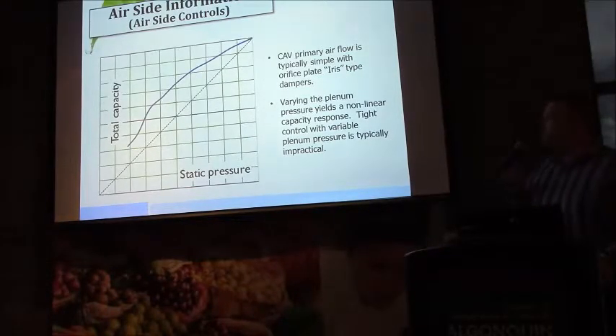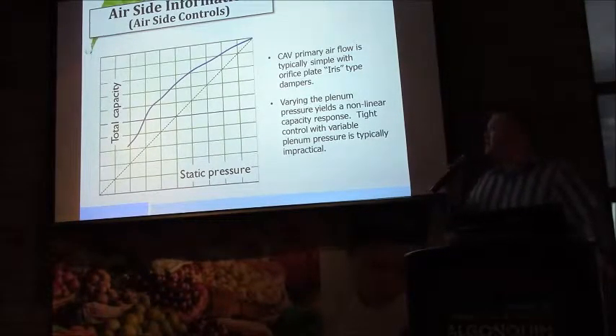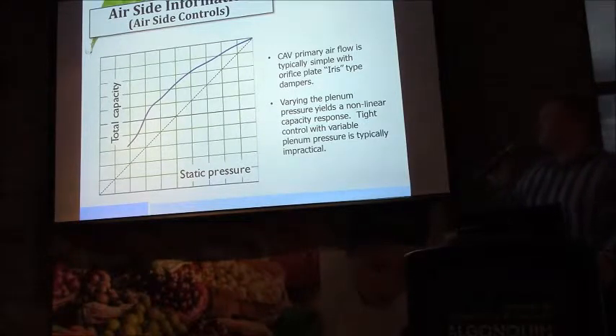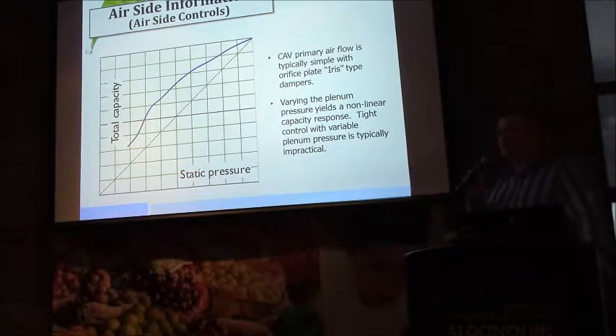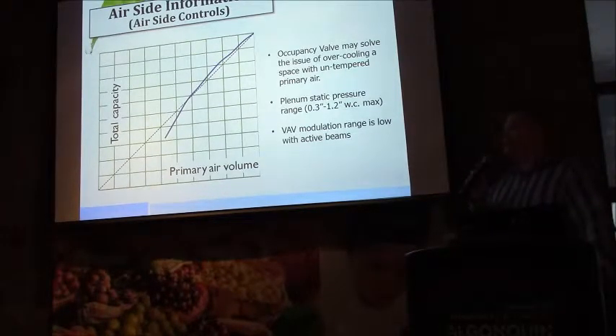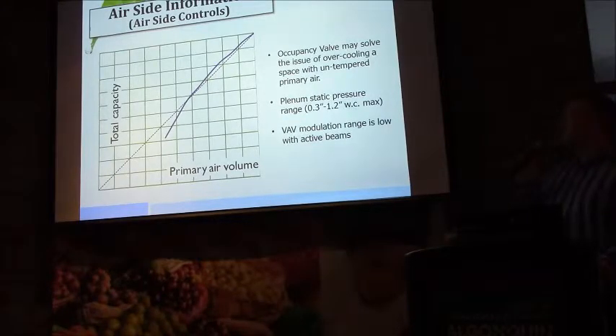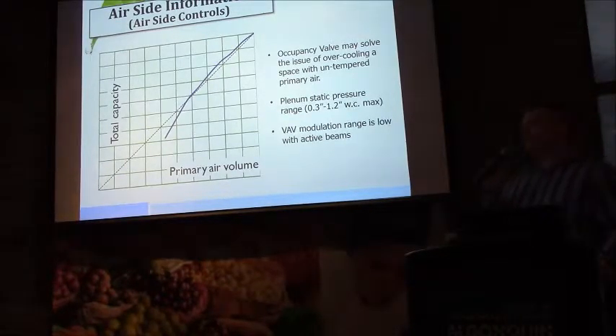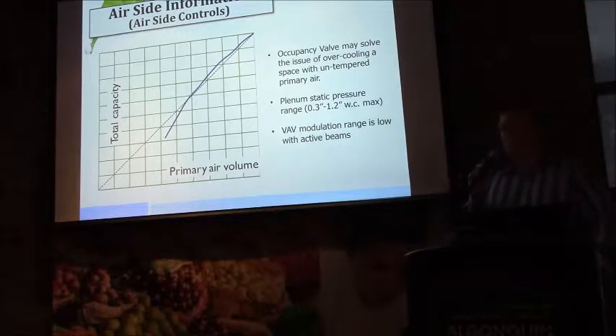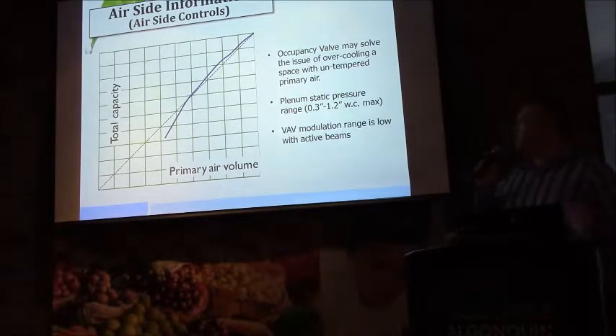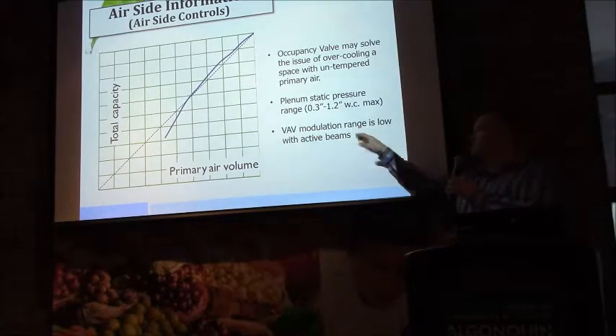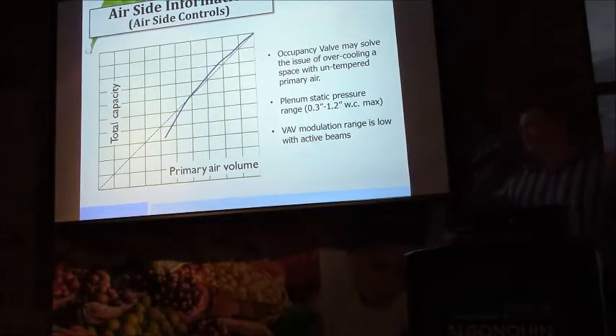We can't modulate the capacity again on static pressure because the response of the beam in terms of thermal performance isn't linear. But if we take the square root of that, we're now into a linear control zone. And again, we could conceivably control the beam on modulating control with a VAV damper. However, the modulation range is small. We would need to select the beam at a much higher static pressure to begin with to ensure greater turndown.